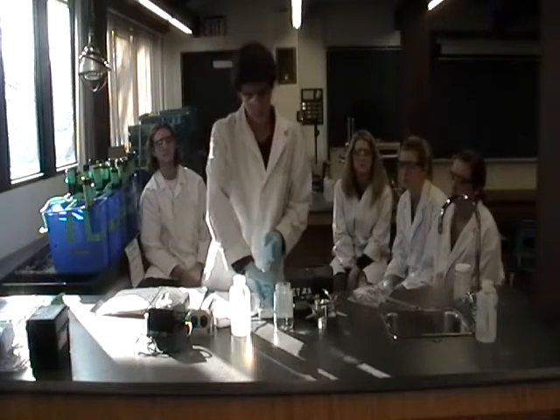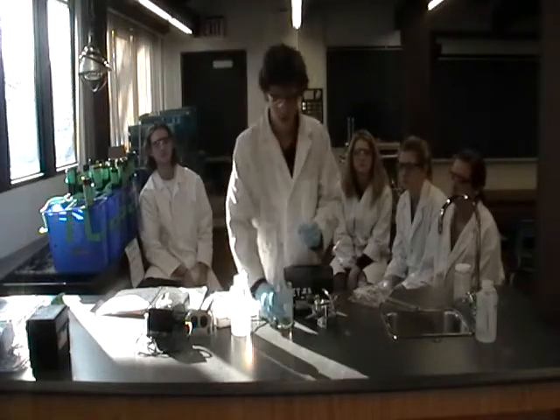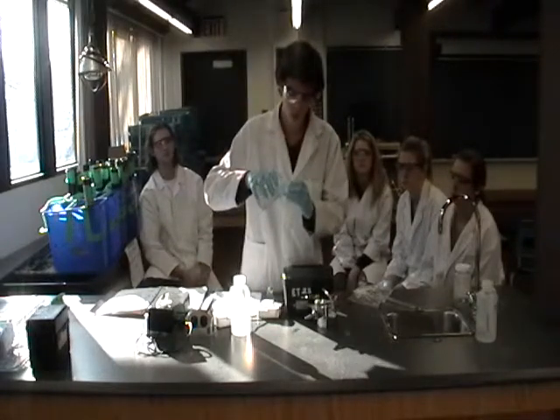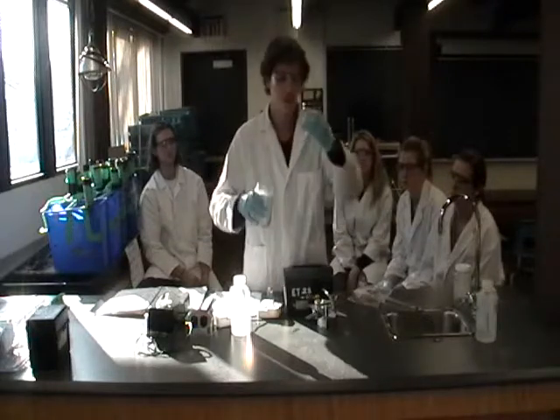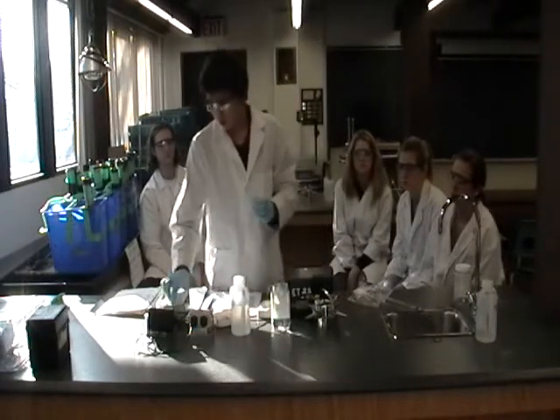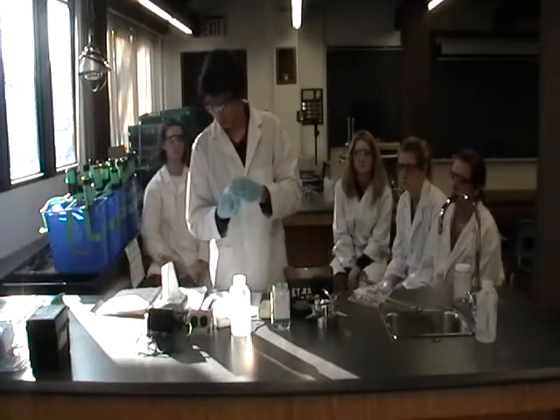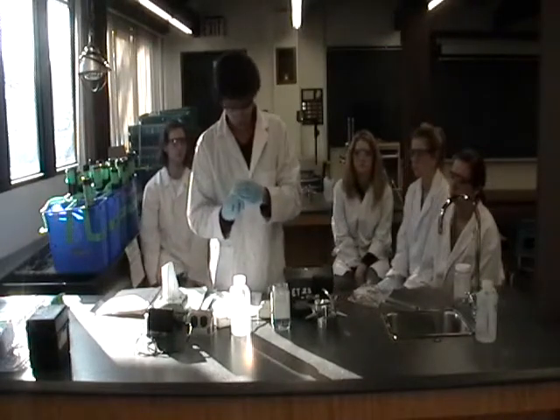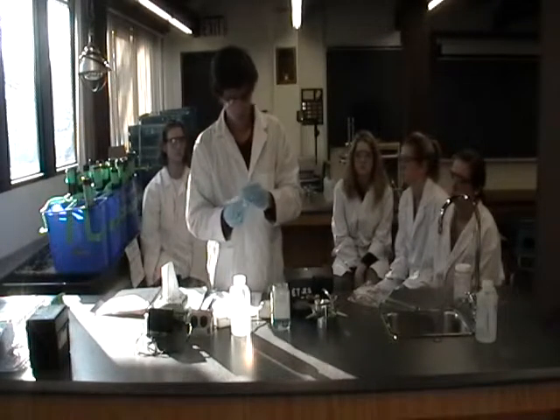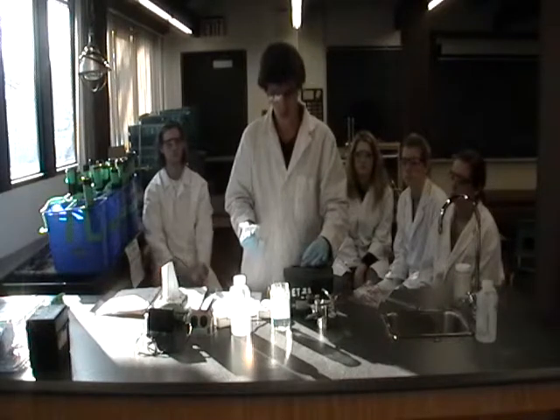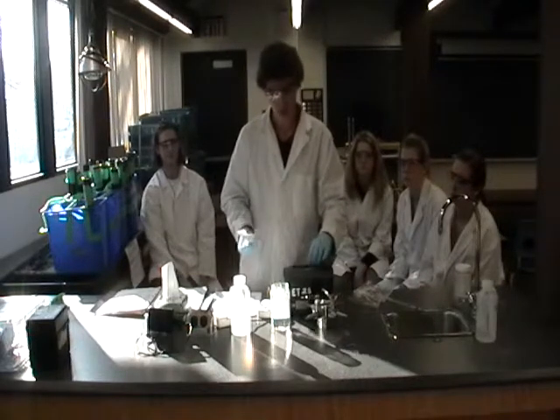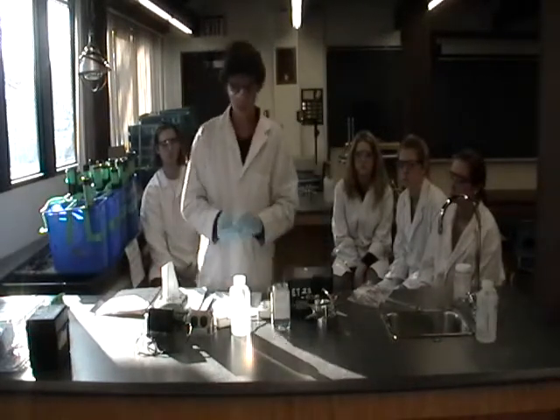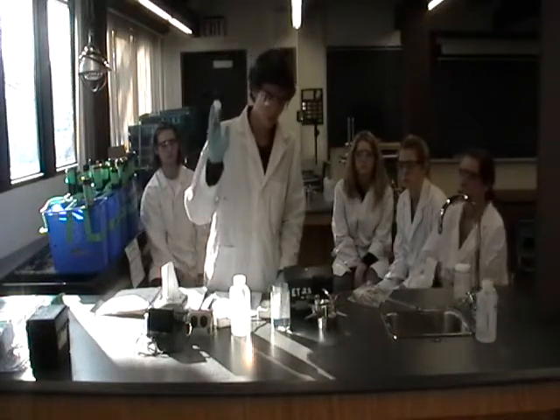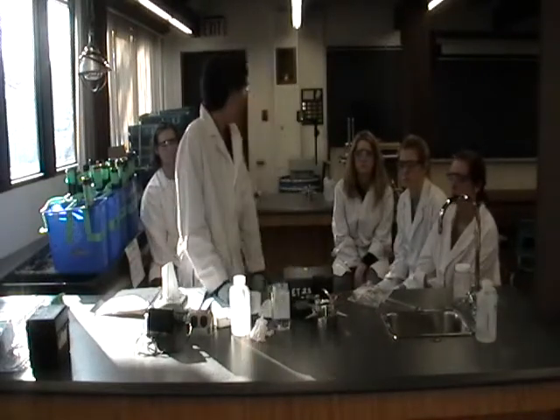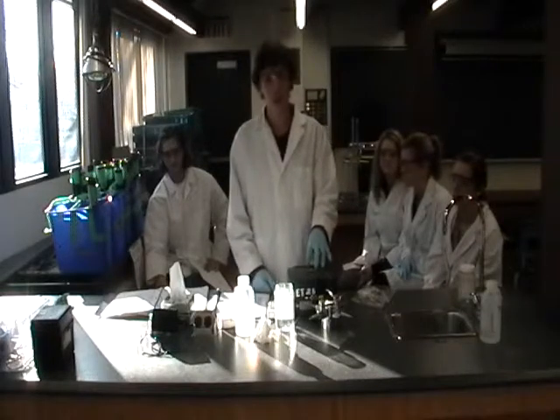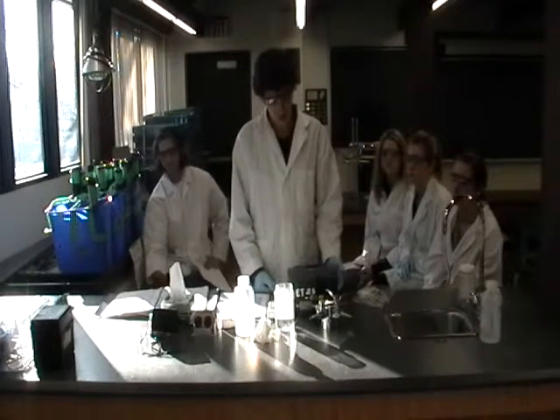And while that's happening, you want to prepare your blank sample. So you pour water in there. And then you want to wipe it off. And then you're ready to put it in, and then you're ready to zero once the timer's up, and then you can do your sample. Now, the timer's up, your blank sample's in here, so you zero the instrument.